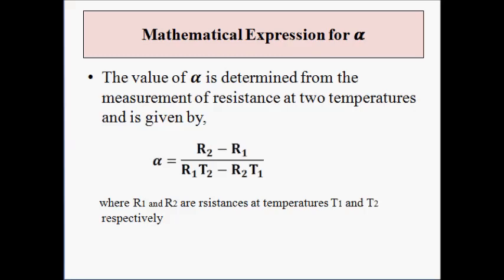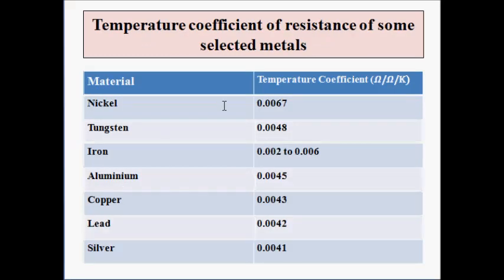Here are some selected metals used for fabrication of RTD with their temperature coefficient alpha values: nickel — 0.0067, tungsten — 0.0048, iron — 0.002 to 0.006, aluminium — 0.0045, copper — 0.0043, lead — 0.0042, and silver — 0.0041.